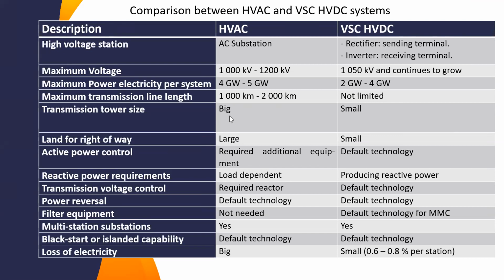For the tower, AC is big, but for VSC it's small. The right of way is large for AC, and small for VSC, because the tower and number of conductors are smaller. Active power control needs additional equipment for AC, but for VSC it's default. Reactive power is load-dependent for AC, while VSC can produce and absorb it at the rectifier—VSC can produce reactive power. For control, AC needs a reactor, but VSC has it as default technology.